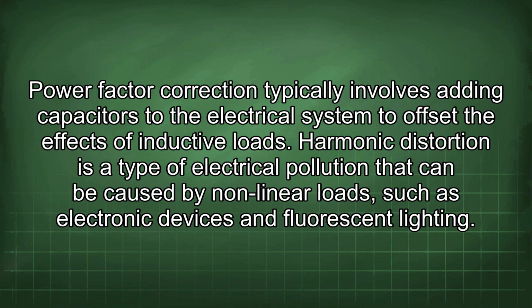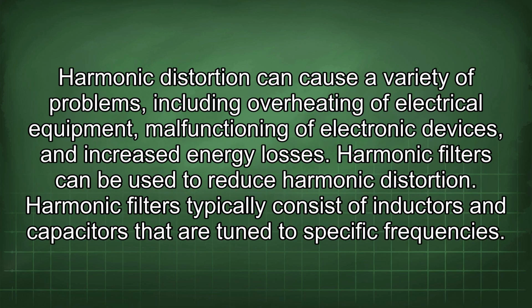Harmonic distortion is a type of electrical pollution that can be caused by nonlinear loads such as electronic devices and fluorescent lighting. Harmonic distortion can cause a variety of problems, including overheating of electrical equipment, malfunctioning of electronic devices, and increased energy losses. Harmonic filters can be used to reduce harmonic distortion. Harmonic filters typically consist of inductors and capacitors that are tuned to specific frequencies.